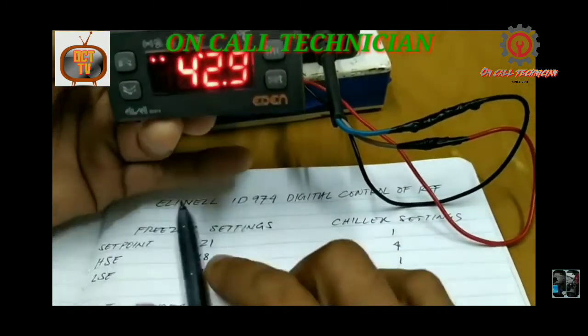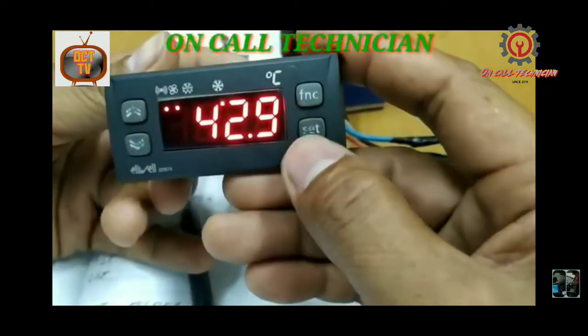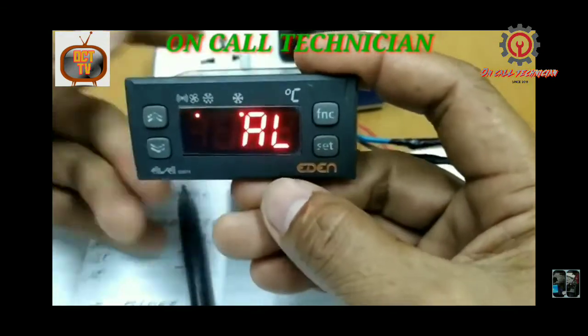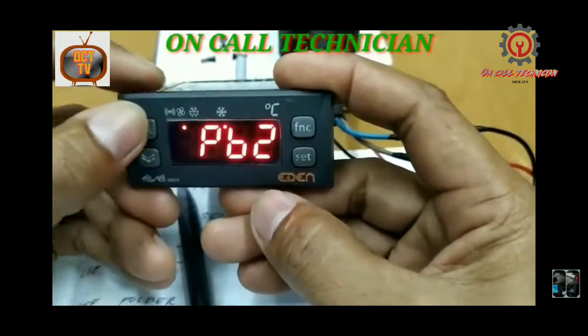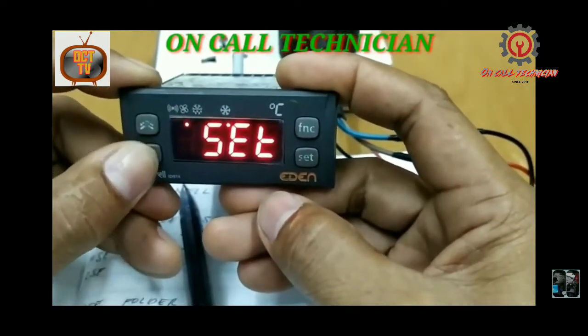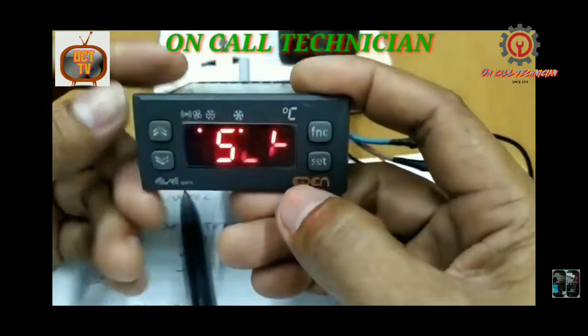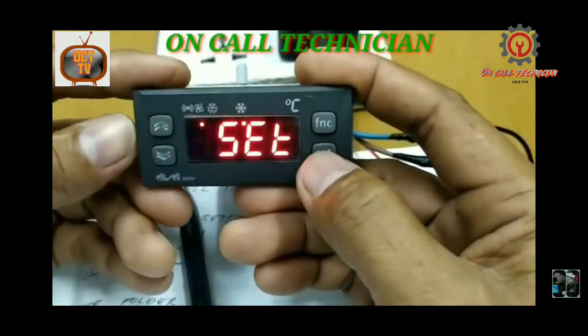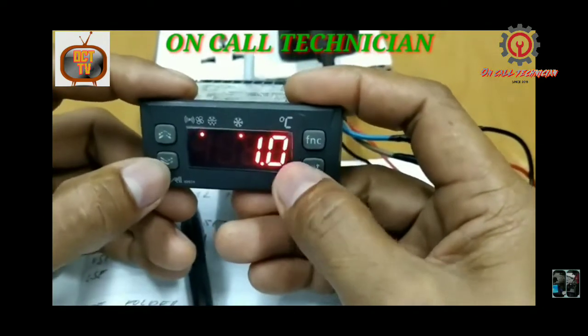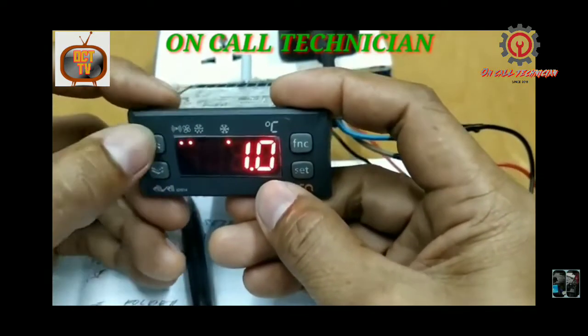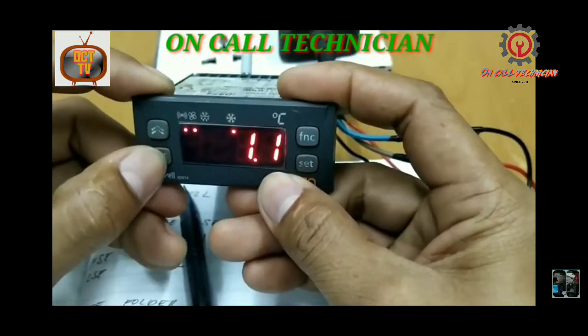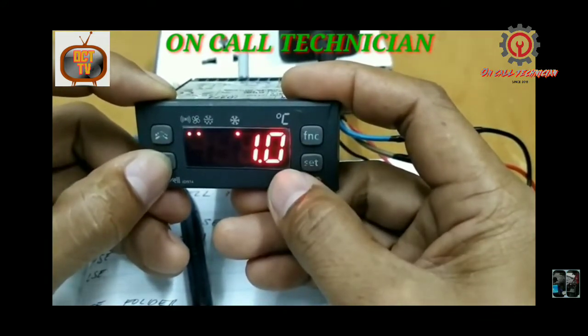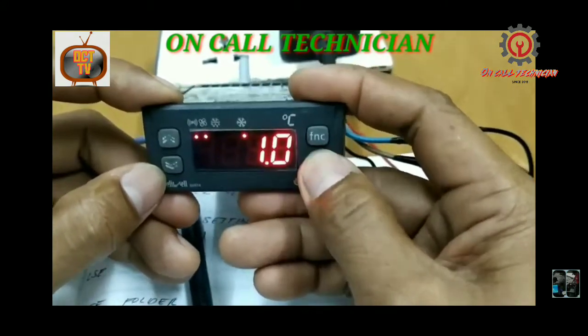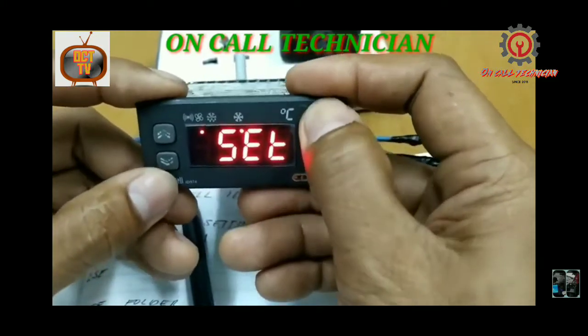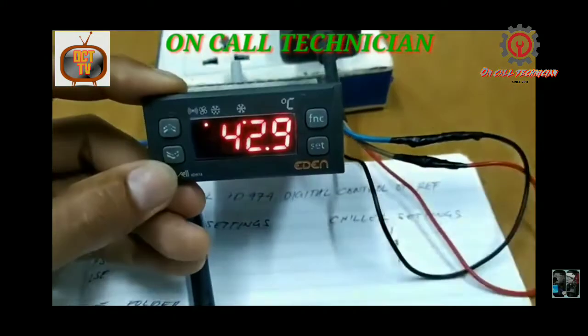Let's enter the parameters again by pressing the set button. This is the set point, guys. Unlike the Dixell, where you need to change the set point, in Eliwell if you change the LSE, it automatically changes.